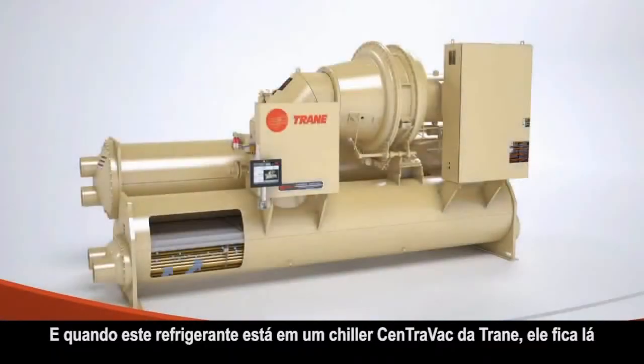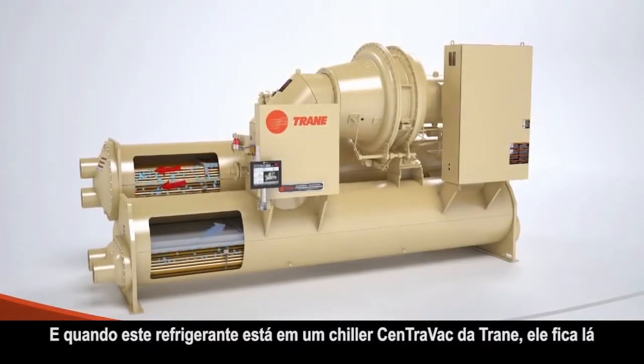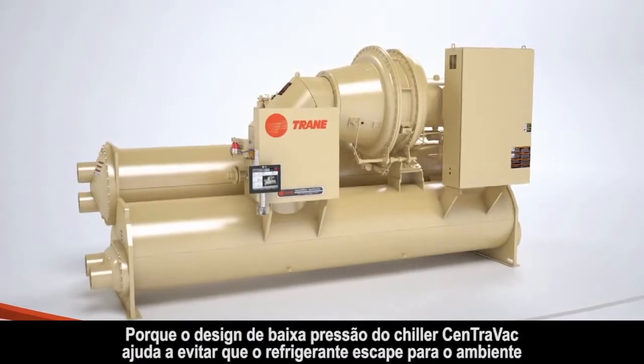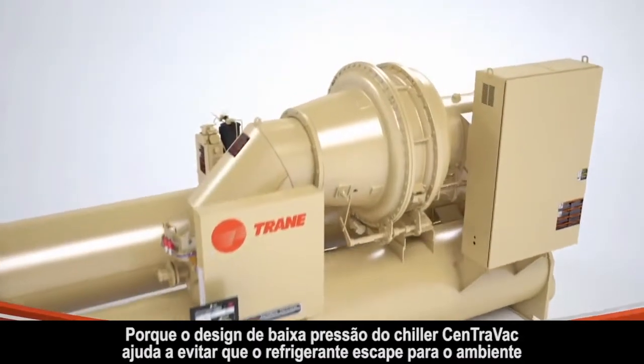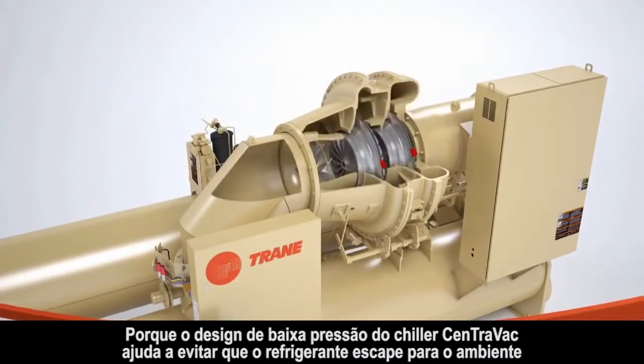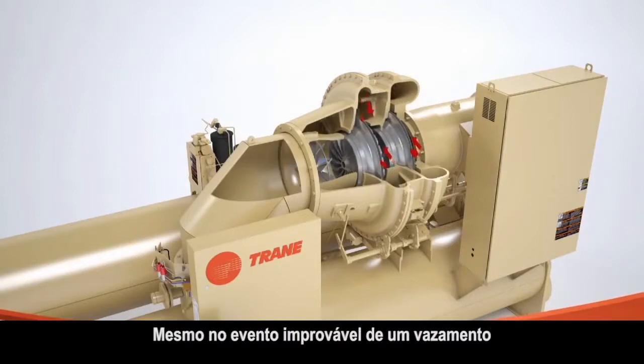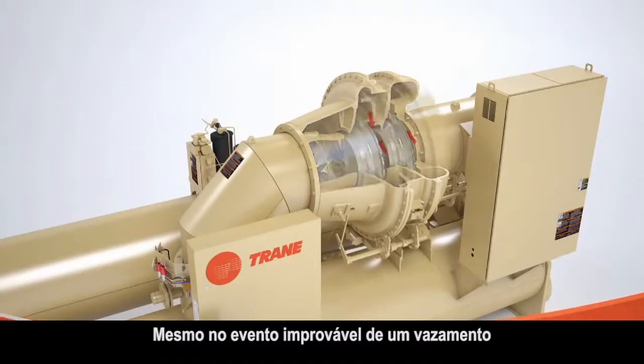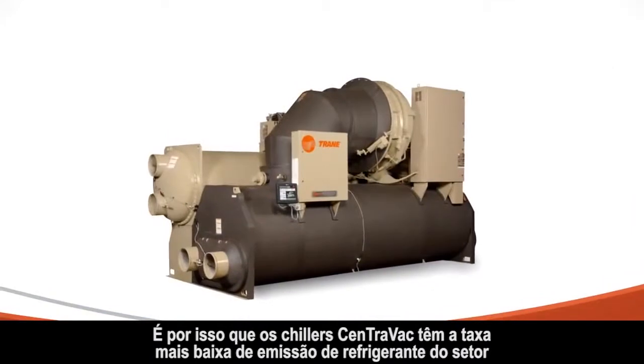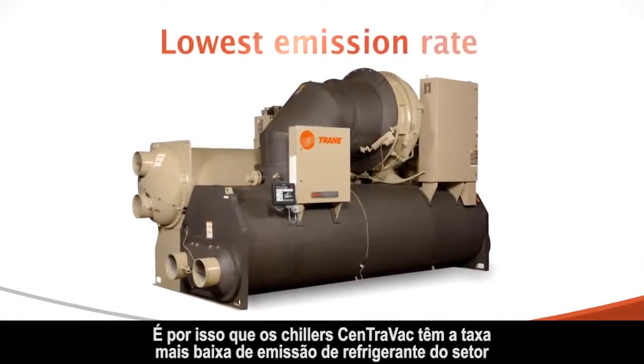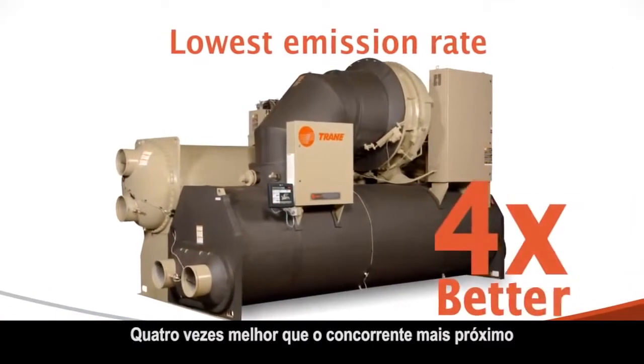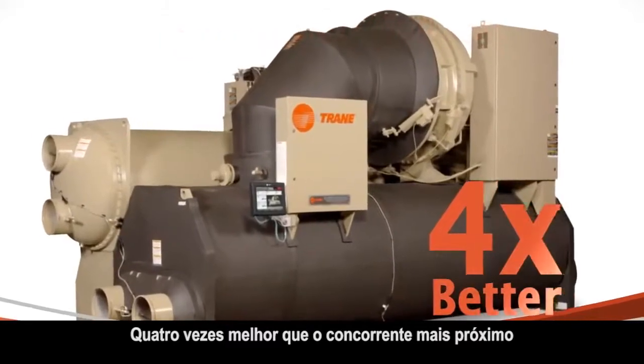Which means half the environmental impact that comes from making, transporting, and using that refrigerant. And when that refrigerant is in a Trane CenTraVac chiller, it stays there, because the chiller's low-pressure design helps keep refrigerant from escaping into the environment, even in the unlikely event of a leak. It's why CenTraVac chillers have the lowest refrigerant emission rate in the industry, 4 times better than the closest competitor.